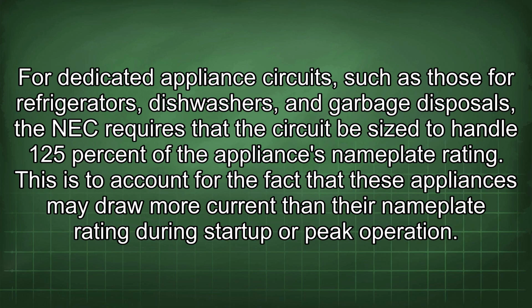For dedicated appliance circuits, such as those for refrigerators, dishwashers, and garbage disposals, the NEC requires that the circuit be sized to handle 125% of the appliance's nameplate rating. This is to account for the fact that these appliances may draw more current than their nameplate rating during startup or peak operation.